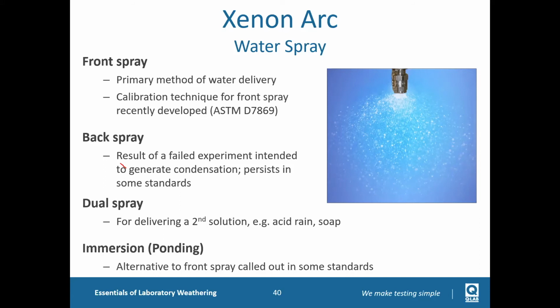Only one test method requires back spray, from my understanding, which is the SAE J2527. In the automotive OEM in North America, when they do exterior testing like paint, they require back spray. Why? Because decades ago, when they did evaluation, they wanted to simulate dew, like condensation. But how can that happen in a xenon chamber? They thought if they spray water on the back side of the panel, it would reduce the panel's temperature, creating a temperature difference.